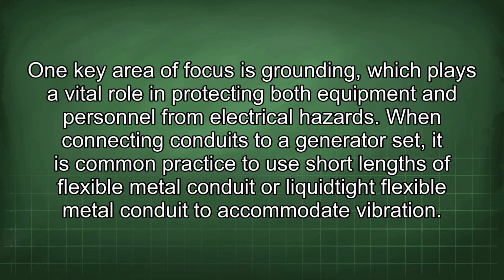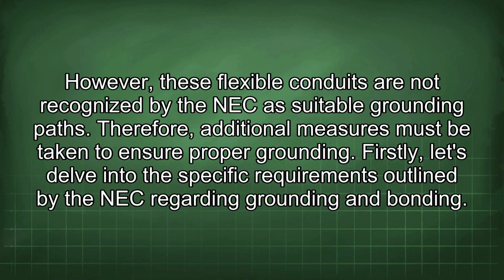One key area of focus is grounding, which plays a vital role in protecting both equipment and personnel from electrical hazards. When connecting conduits to a generator set, it is common practice to use short lengths of flexible metal conduit or liquid-tight flexible metal conduit to accommodate vibration. However, these flexible conduits are not recognized by the NEC as suitable grounding paths. Therefore, additional measures must be taken to ensure proper grounding.